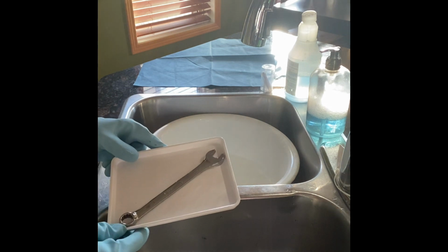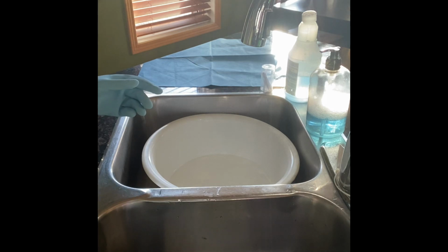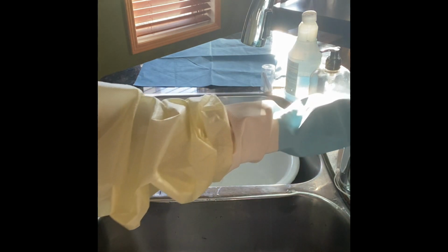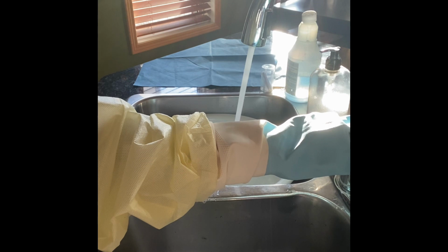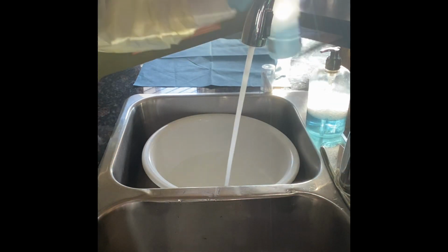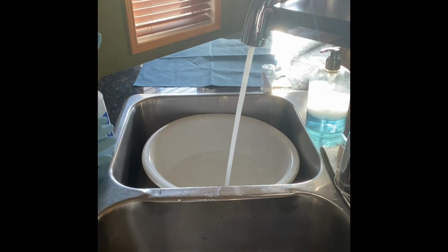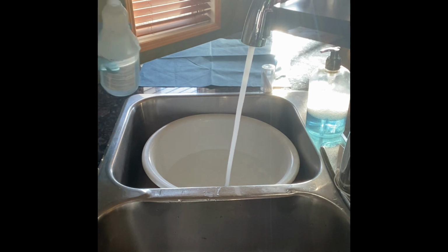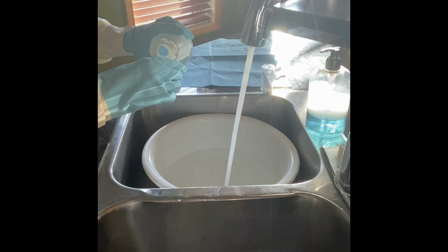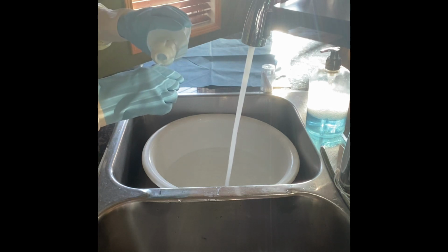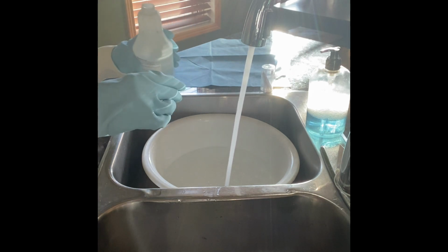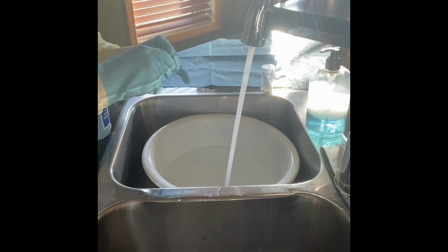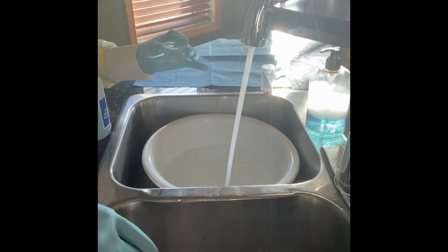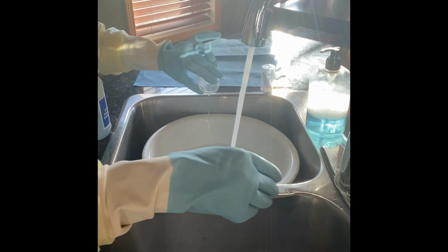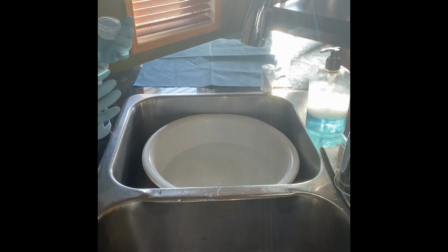Pre-clean the instrument to remove any organic contents to discard in proper container. All medical equipment must be cleaned first, using water and detergents prior to any subsequent disinfection or sterilization. Using enzymatic solutions like Medzyme as a detergent, please adhere to manufacturer's instructions for preparing solutions and use measuring devices or methods to ensure consistent concentrations.